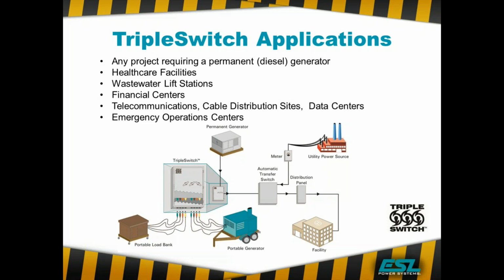because of the phenomenon of wet stacking, because the diesel fuel doesn't burn clean, doesn't get hot enough because it's never run under a load, whereas natural gas is very clean burning, so the generators don't have a tendency to wet stack and get sort of hardening of the arteries. But a lot of the generator providers do suggest that even natural gas generators be load banked under a load at least once a year, just to test the full functionality of the generator. So we do a number of natural gas ones as well.